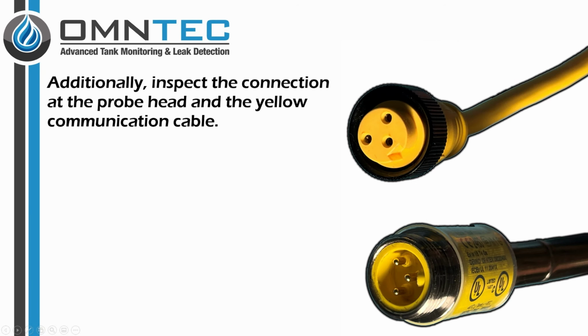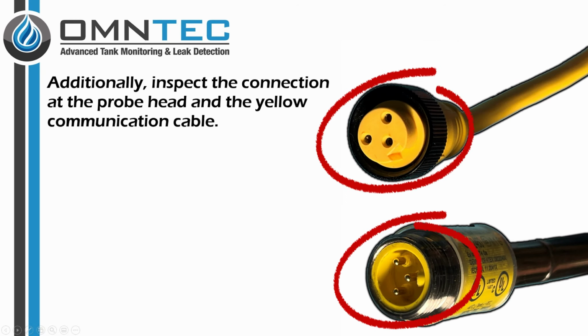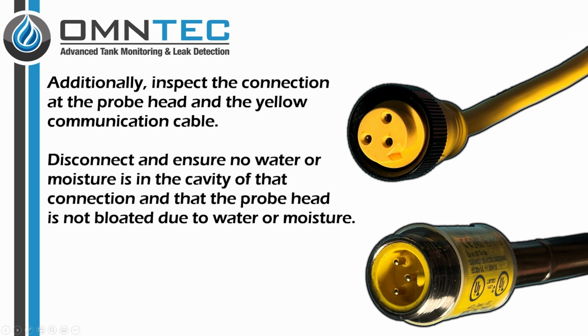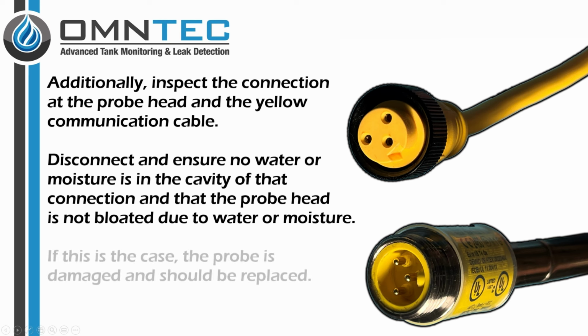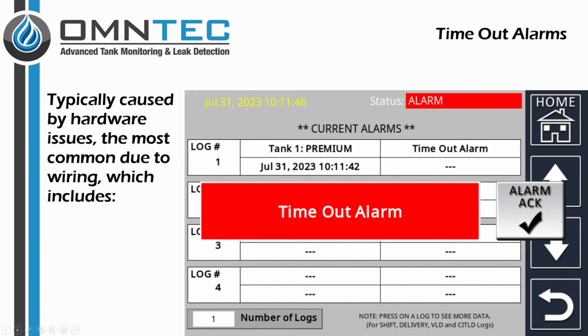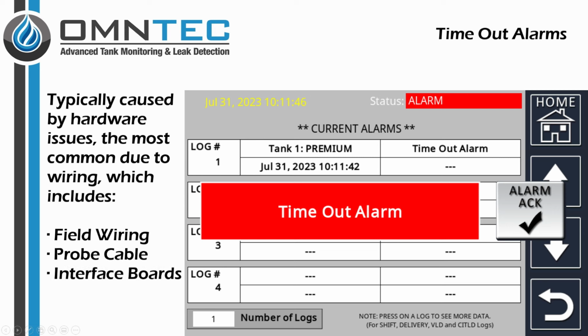Additionally, inspect the connection at the probe head and the yellow communication cable. Disconnect and ensure no water or moisture is in the cavity of that connection and that the probe head is not bloated due to water or moisture. If this is the case, the probe is damaged and should be replaced. Timeout alarms are typically caused by hardware issues, the most common due to wiring, which includes field wiring, probe cable, interface boards, and junction box connections.